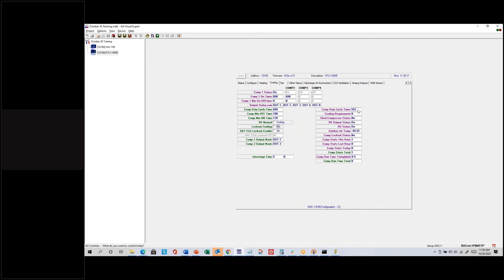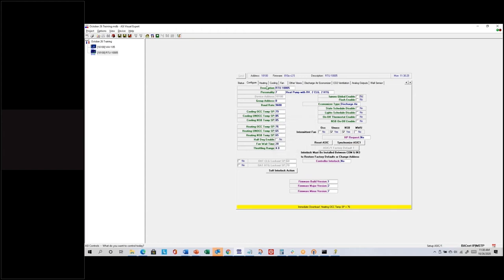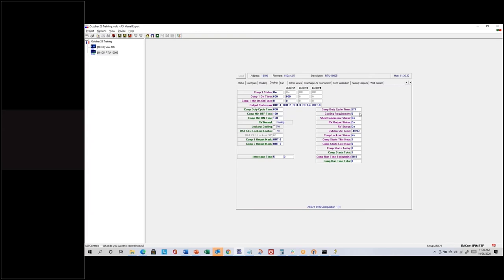I'll change my set points so the system doesn't stay on indefinitely. On the configure tab, I'll lower the heating set point to 76. On the cooling tab, once the duty cycle counts up to 600 and restarts — compressor 2 is actually on because it calculated to be on indefinitely. Now let's show that it will turn off.